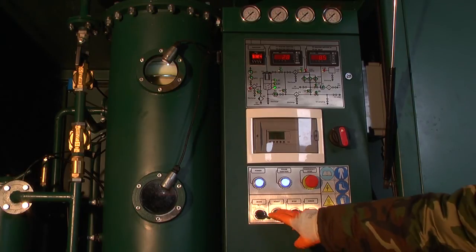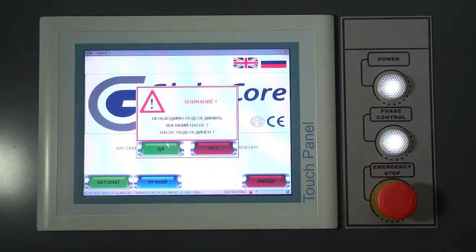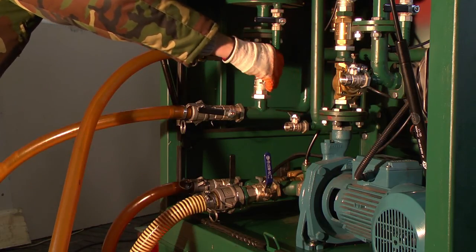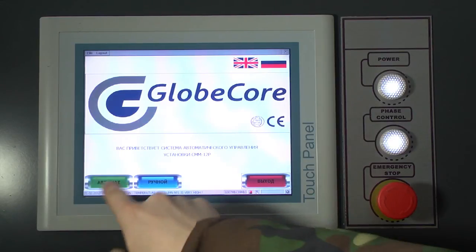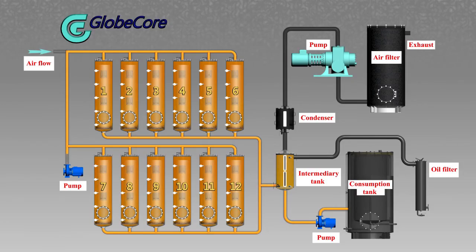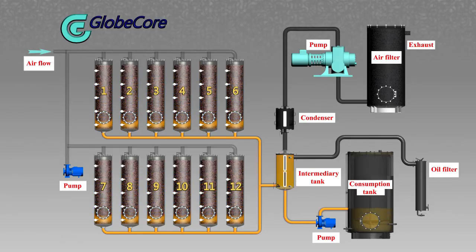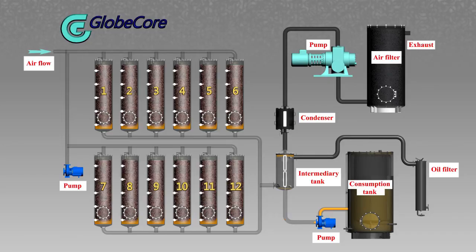After start, the units operate automatically with all process parameters adjusted by the automation system. When sorbent reactivation is required, the bypass line is closed and the operator initiates the sorbent reactivation process. The output pump drains the oil from sorbent columns and puts it into the buffer tank. After the columns are completely drained, the vacuum pump starts, creating airflow for the columns. Then the sorbent surface heater switches on. Sorbent reactivation starts and all absorbed decomposition products are extracted. When the reactivation process ends, the heating system switches off.